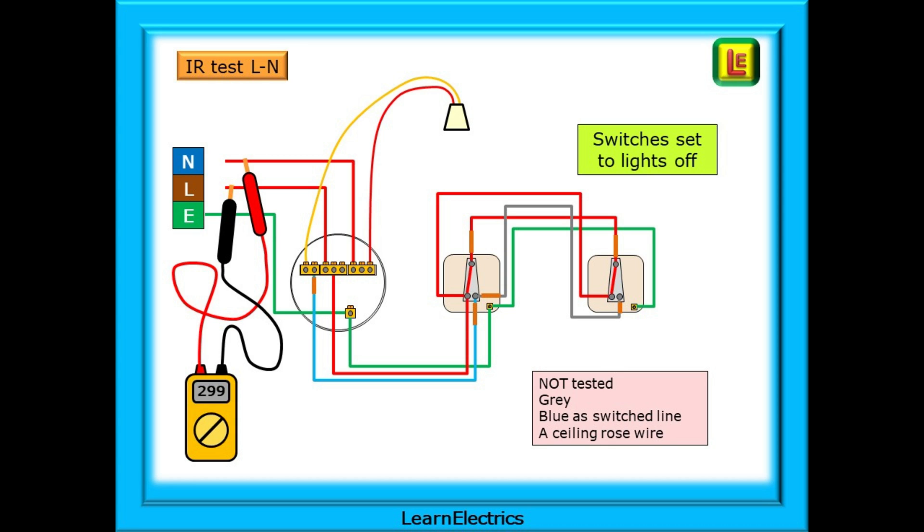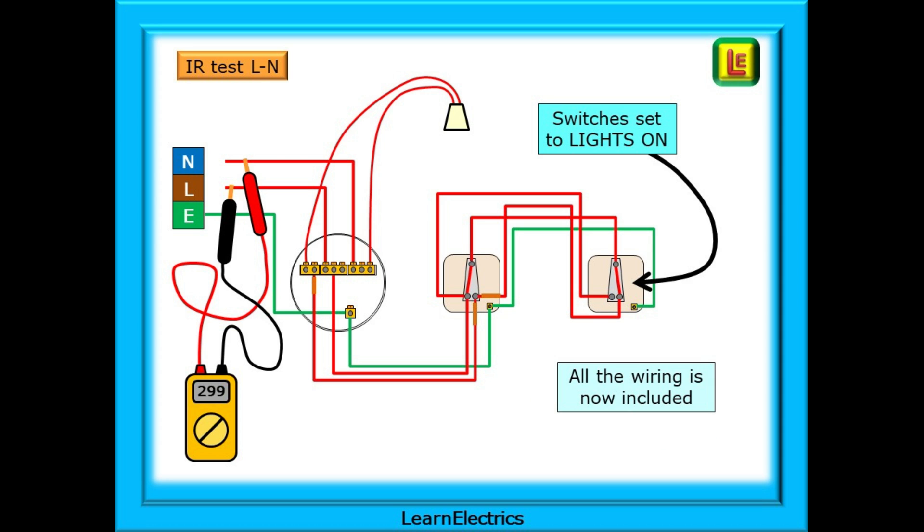Now put the probes onto the line and neutral wiring. Again, with the switches set to the lights off position, the red coloured wires are the ones being tested. With the switches set to lights on, all the line and neutral wiring is being tested and hopefully you can see the importance of always doing two IR tests for each wiring combination. By testing once and then operating just one light switch and testing a second time, you can be certain that you've included all the circuit conductors for that test.